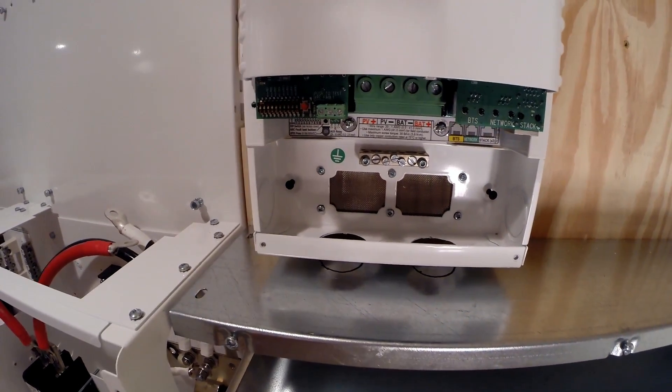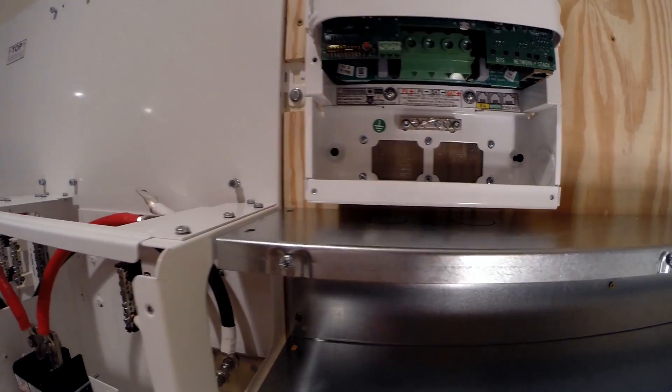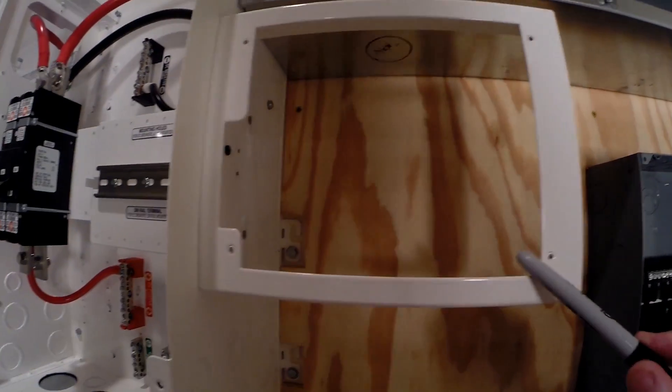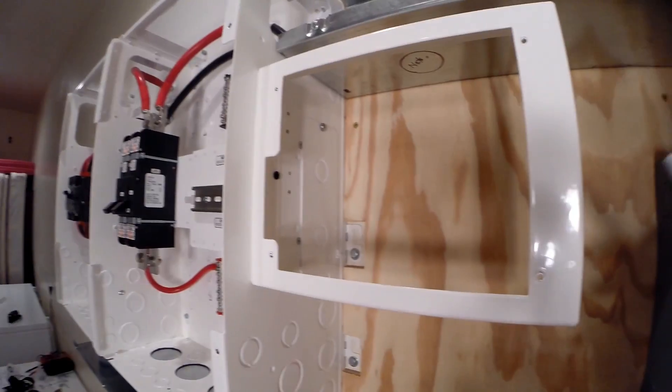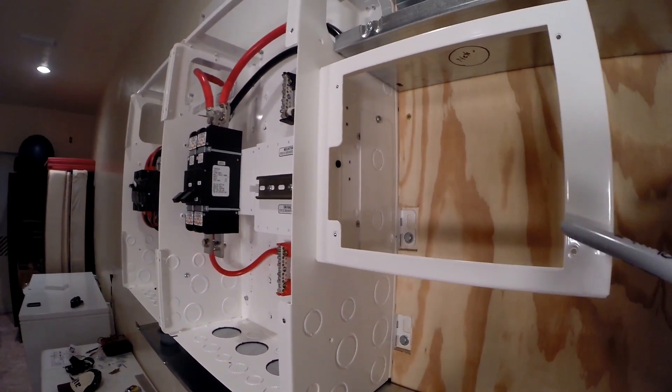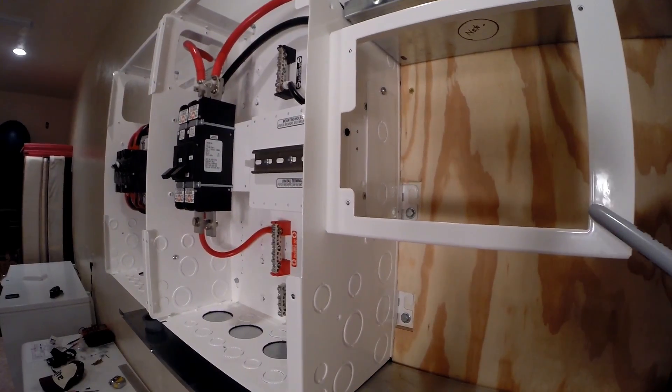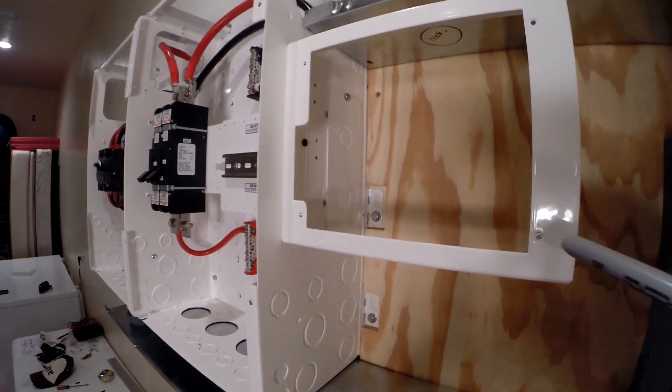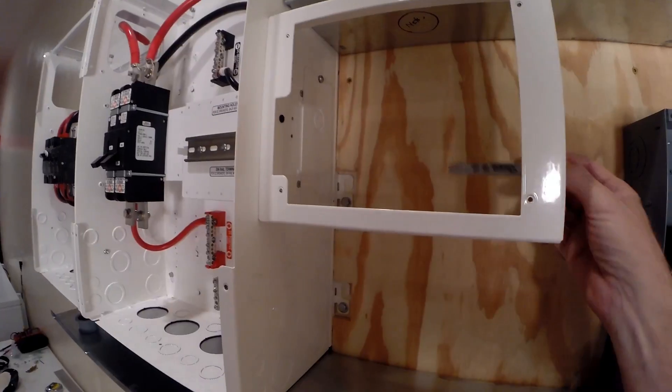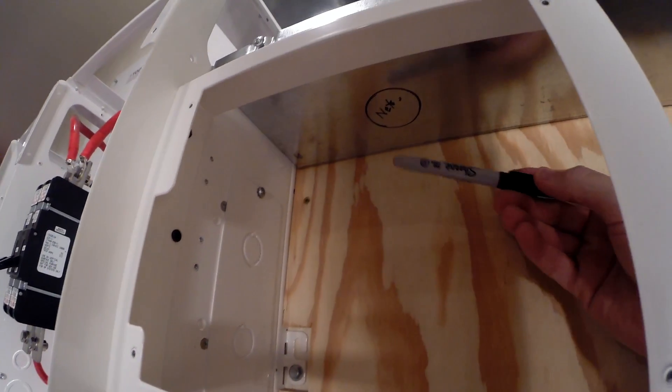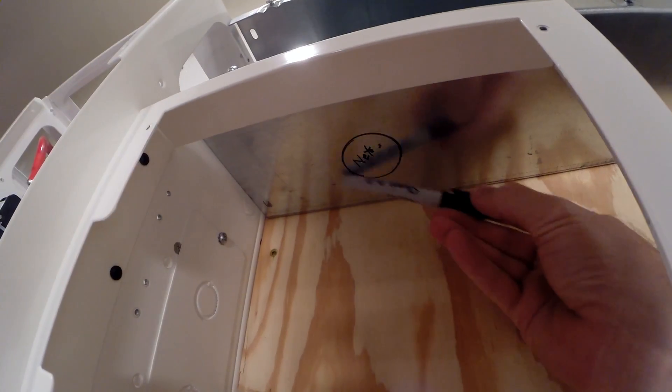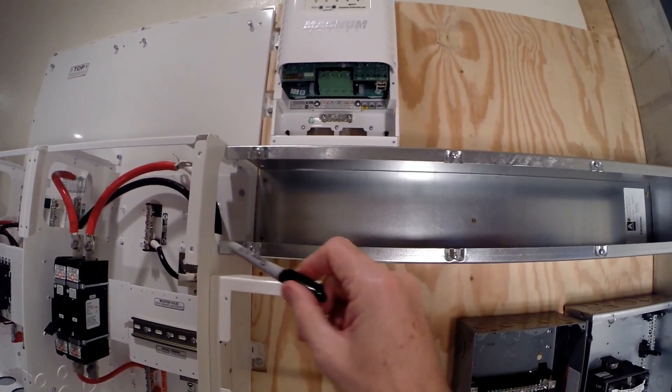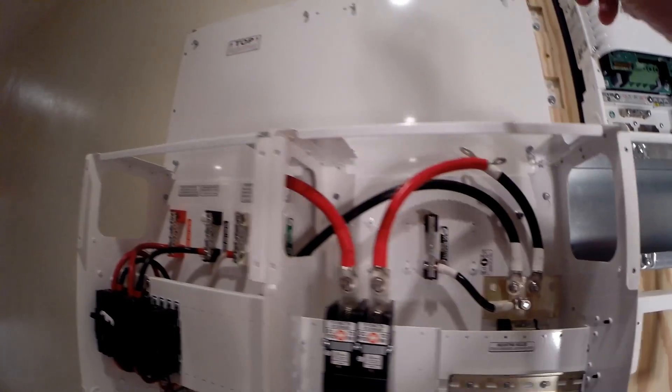The router is going to go here - it's how you program it and I can see what's going on. This has probably four or five Cat5 cables, network cables, RS-422 cables - various cables coming out of here. I'm gonna have them go up through the back and run up through this knockout. I'll put a 2-inch hole here so that'll keep everything out of sight. From there it goes into the cable tray and can run wherever they need to run - most of them going to the two inverters up here, the charge controller, some to battery temperature sensors and so on.